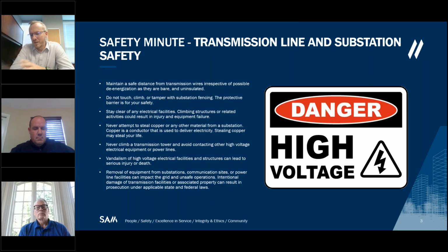The bullet points here are mostly public facing, like information about not approaching electrified or energized substations. But to drive home the point with FAC-008, when our crew or any field crew is inside a substation, it's important to adhere to minimum approach distances to energized equipment. So for our personnel, if we're bringing equipment inside a substation that has any height to it, we'll perform a minimum approach distance calculation. We'll look at the voltage levels and refer to the NESC for what those minimum approach distances are, to make sure we're operating safely.